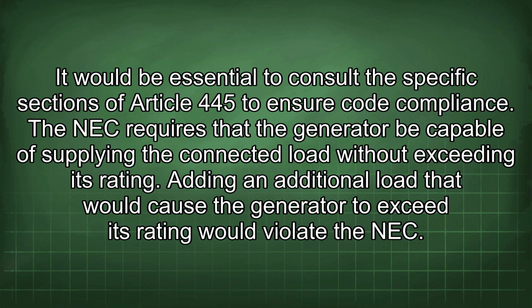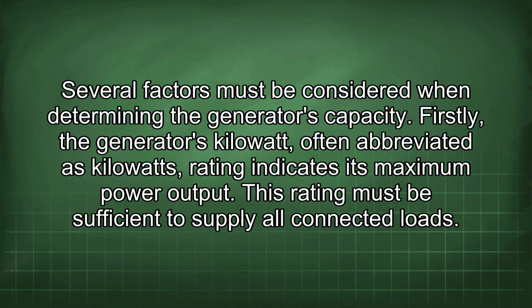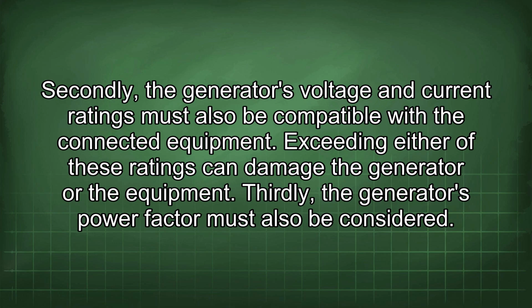The NEC requires that the generator be capable of supplying the connected load without exceeding its rating. Adding an additional load that would cause the generator to exceed its rating would violate the NEC. Several factors must be considered when determining the generator's capacity. Firstly, the generator's kilowatt rating indicates its maximum power output. This rating must be sufficient to supply all connected loads. Secondly, the generator's voltage and current ratings must also be compatible with the connected equipment. Exceeding either of these ratings can damage the generator or the equipment.